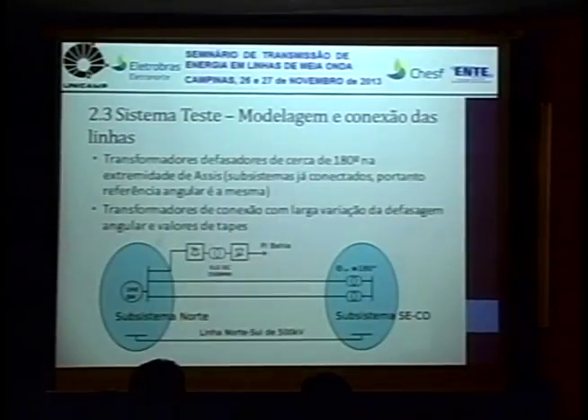This came already done from EPE. It was a ready model that is being used to represent a half-wavelength link using 35 pi segments in series. Only for the 1000 kV line we did the configuration and included it, because in the EPE report there were only two alternatives, two lines of 800 kV and other lines with 600 kV, but we also included two lines of 1000 kV in the system. But always using 35 pi segments in series with a total length of 2,644 kilometers, leaving Altamira and reaching the city of Assis.